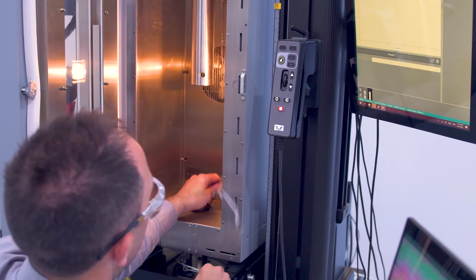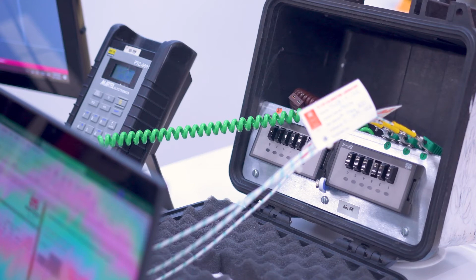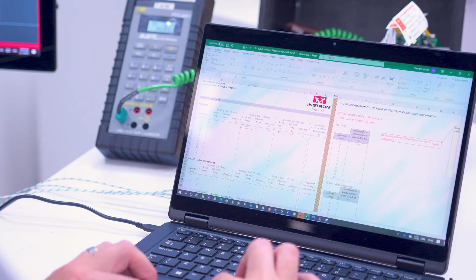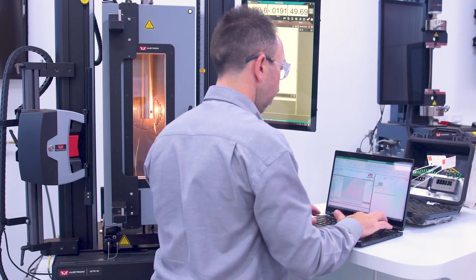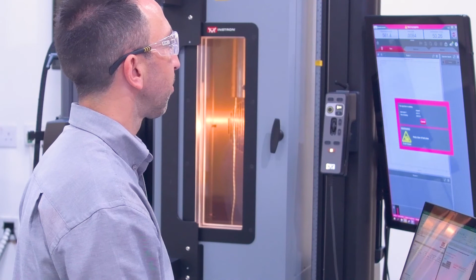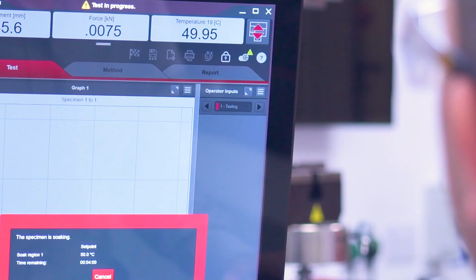The second calibration service is referred to as sensor substitution and consists of injecting calibrated signals into the instrument being verified. This simulates a correctly performing thermocouple, millivolt, or RTD, and provides a reference for the sensor being verified.